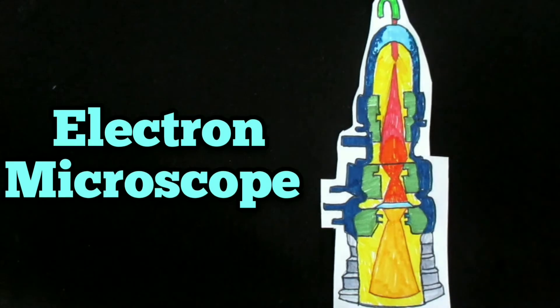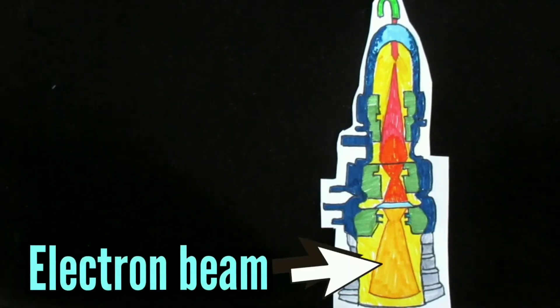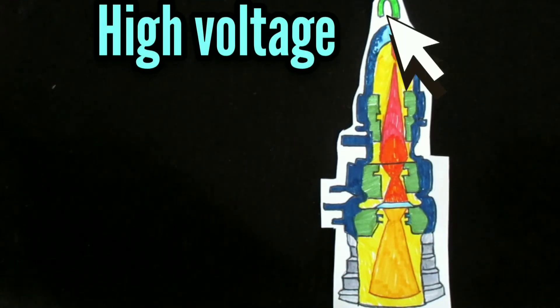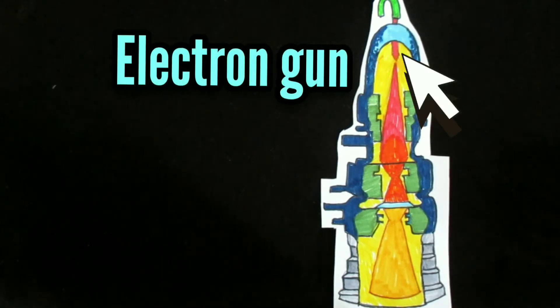Electron microscopes consist of a tall hollow cylindrical column through which the electron beam passes. The top of the column contains the cathode, a tungsten wire filament that is heated to provide a source of electrons.